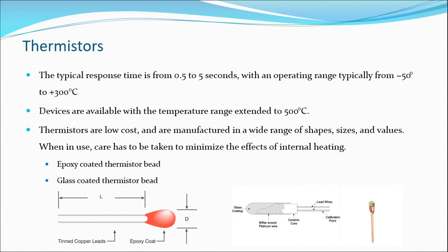It is critical that NTC thermistors are protected from direct exposure to fluids such as water and oil. To accomplish this, thermally conductive epoxy is used as an encapsulant, called potting, to seal the NTC thermistors. Temperature sensors in stainless steel housings are also available, but epoxy not only protects the NTC sensors from moisture but also enables good thermal conduction from the medium being measured to the thermistor sensors.